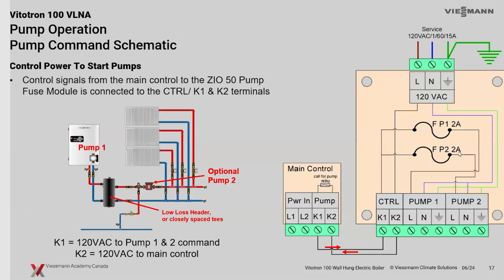And if we were to look at that, the main power comes in. K1, K2 is a pump relay. It closes, of course, and that power goes through parallel through the 2 amp fuses. So pump 1 and pump 2 have their power output coming from this little relay contactor first, allowing the power to go through to those contacts on the bottom. So we power through here. If you follow that little L, it goes from K2 up around. It has to close here first, up through K1, and then we power up through our fuses here to operate those little circulators. So a little conceptual drawing here on the left-hand side of what that might look like.